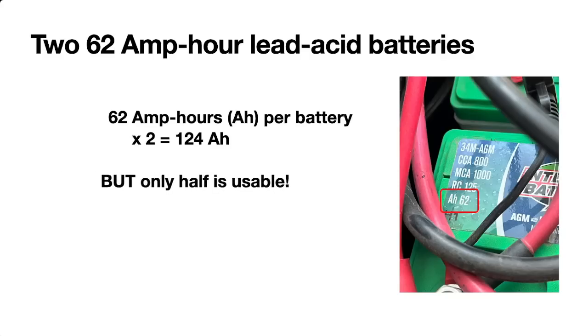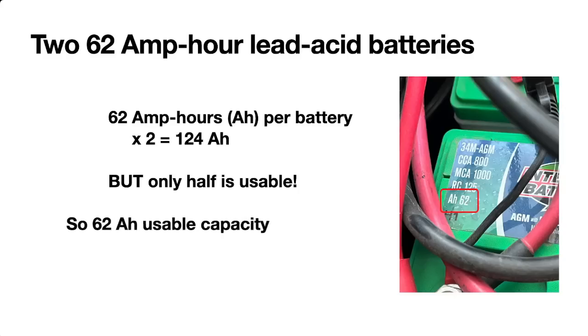You might think you've got 124 amp hours of battery capacity with two batteries, but in fact you don't, because these are lead acid batteries. They really should only be discharged about 50% of their rated capacity. So even though you've got two batteries at 62 amp hours each, you really still only have 62 amp hours of usable capacity.